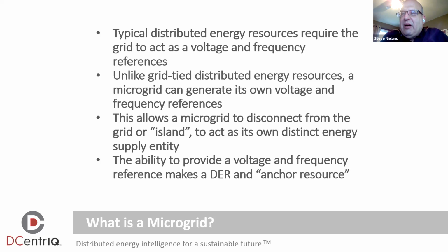Now, there were a lot of power plants in there outside of that, but the problem is those power plants relied on the grid, and when the grid went down, there was nothing the power plant could use for a voltage and frequency reference, so it couldn't start up until its section of grid saw power again.